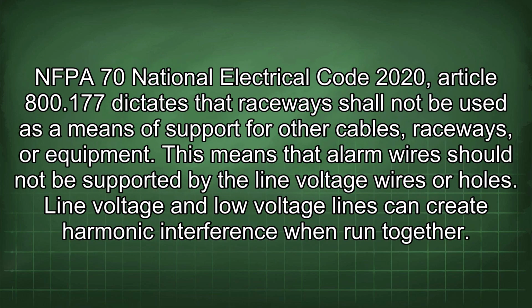NFPA 70, National Electrical Code 2020, Article 800.177 dictates that raceways shall not be used as a means of support for other cables, raceways, or equipment. This means that alarm wires should not be supported by the line voltage wires or holes.